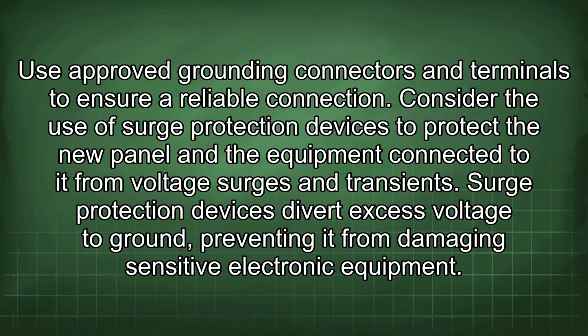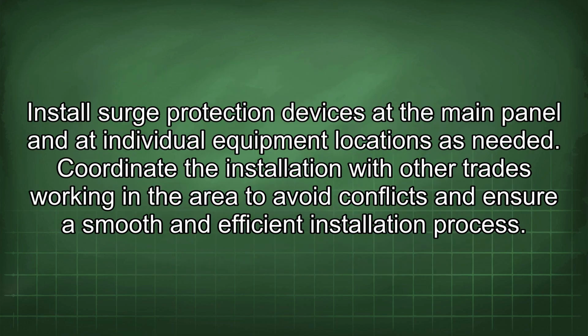Consider the use of surge protection devices to protect the new panel and the equipment connected to it from voltage surges and transients. Surge protection devices divert excess voltage to ground, preventing it from damaging sensitive electronic equipment. Install surge protection devices at the main panel and at individual equipment locations as needed.